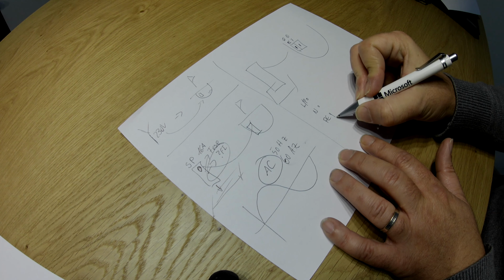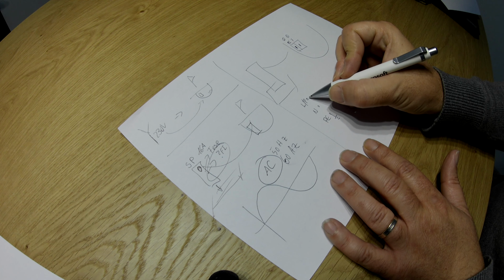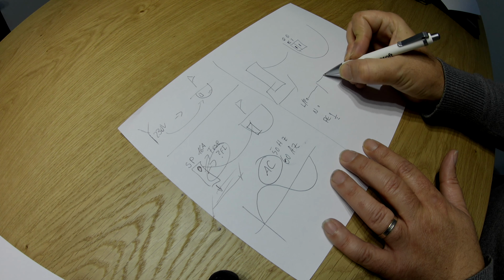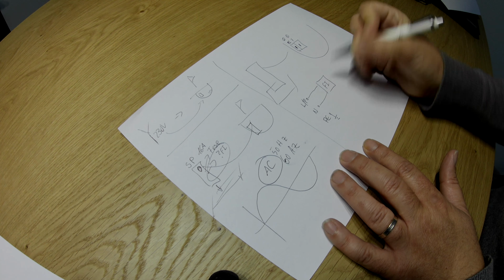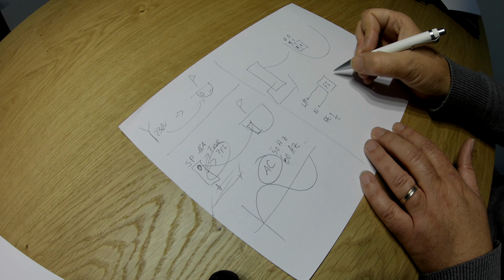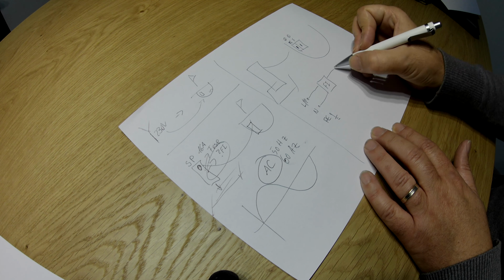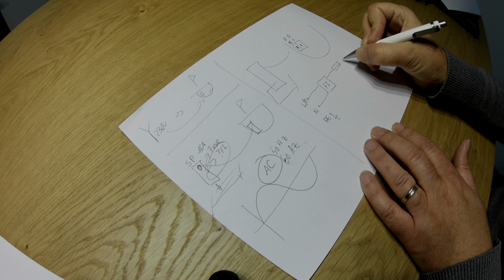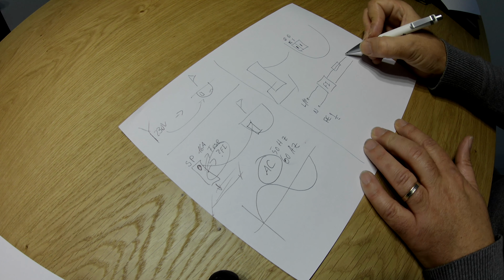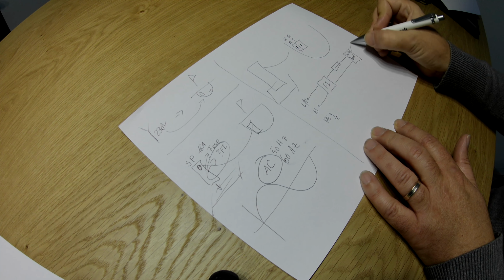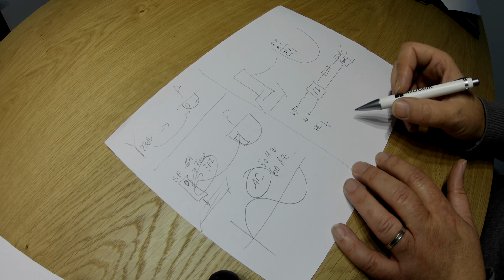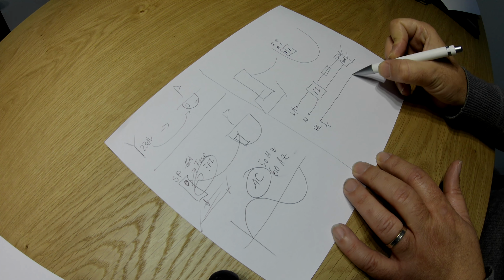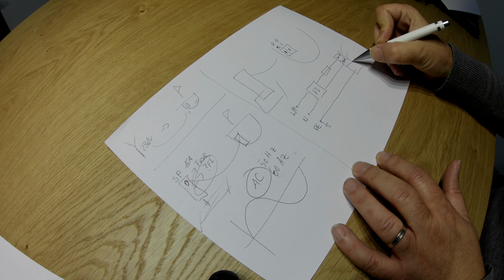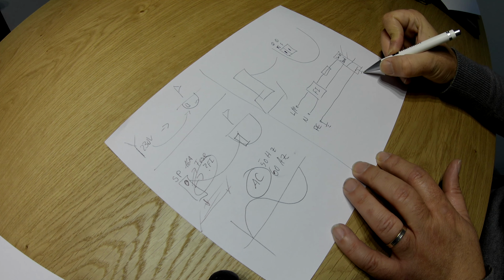Then we go into our FI - I use the German shortcut because then I only need 2 letters. On the next side, we put our normal fuse, and from here we put our switchboard, and then you can distribute to wherever you want. Now we put also the PE, and that's important. I extend our switchboard because the PE is the same thing - you ground it, and then you can distribute it to all devices which you need to power with 230 volts.